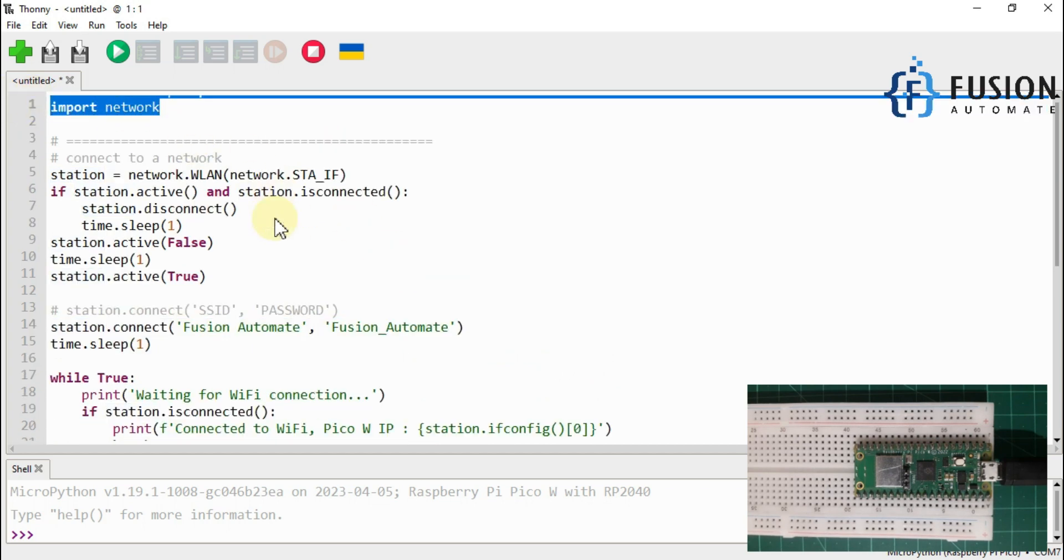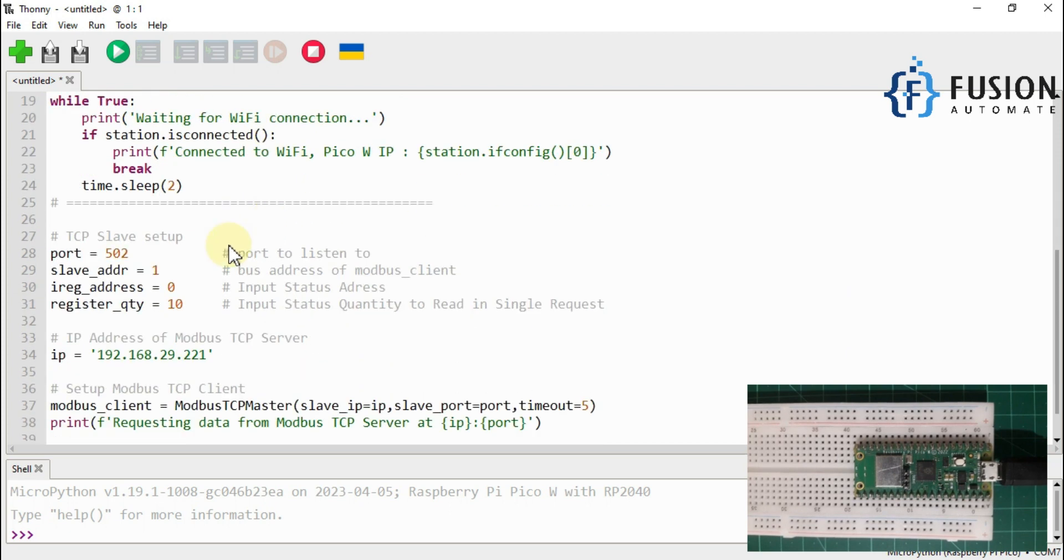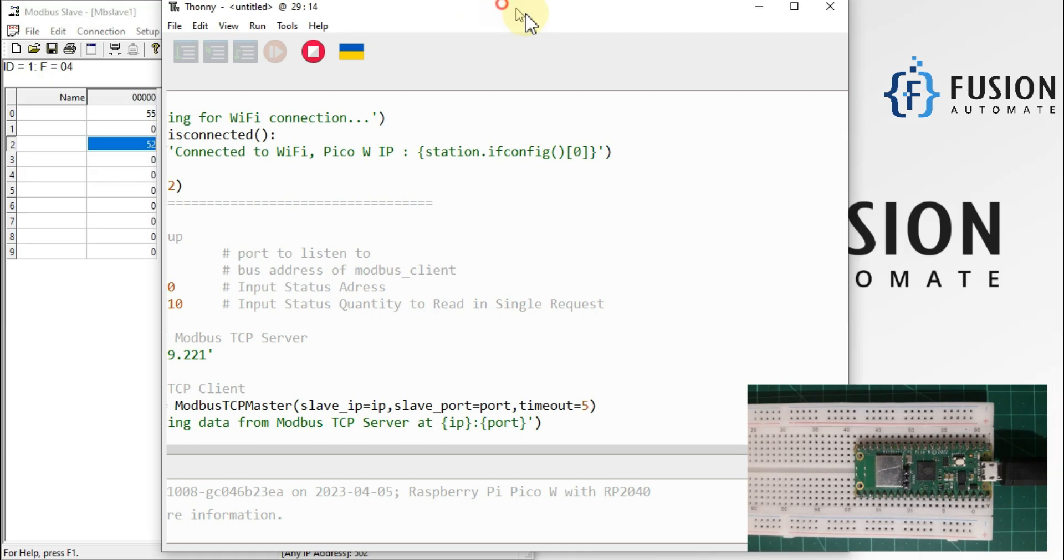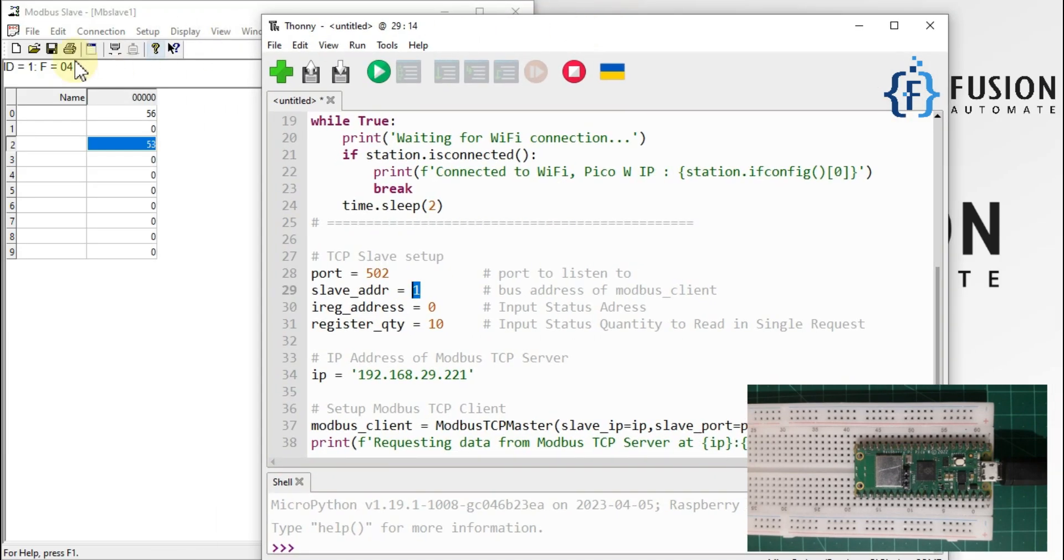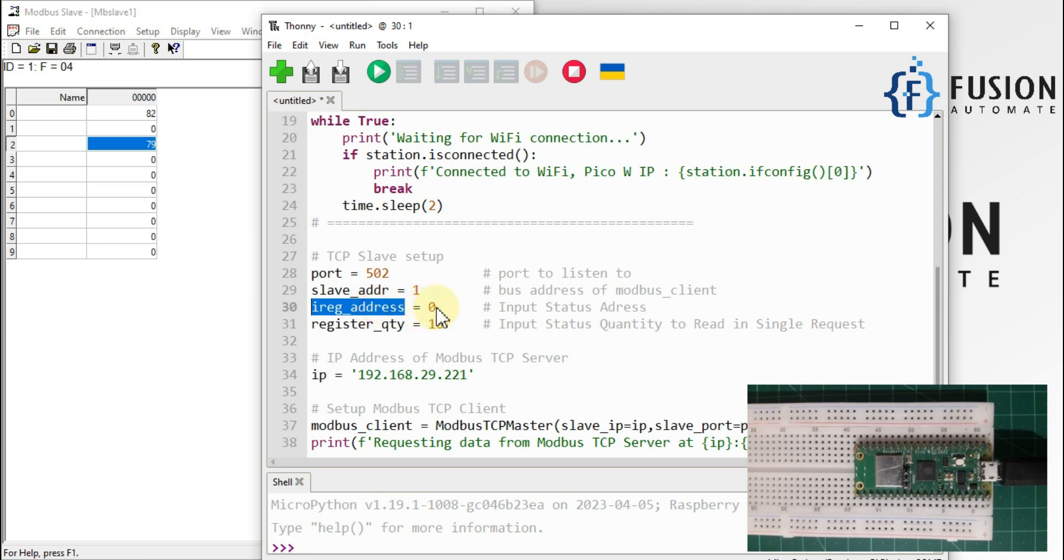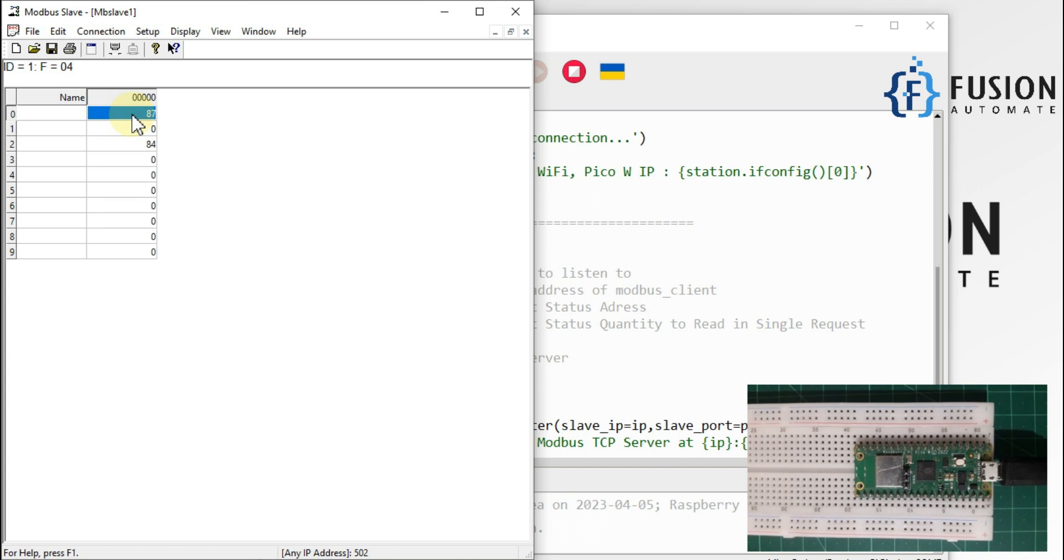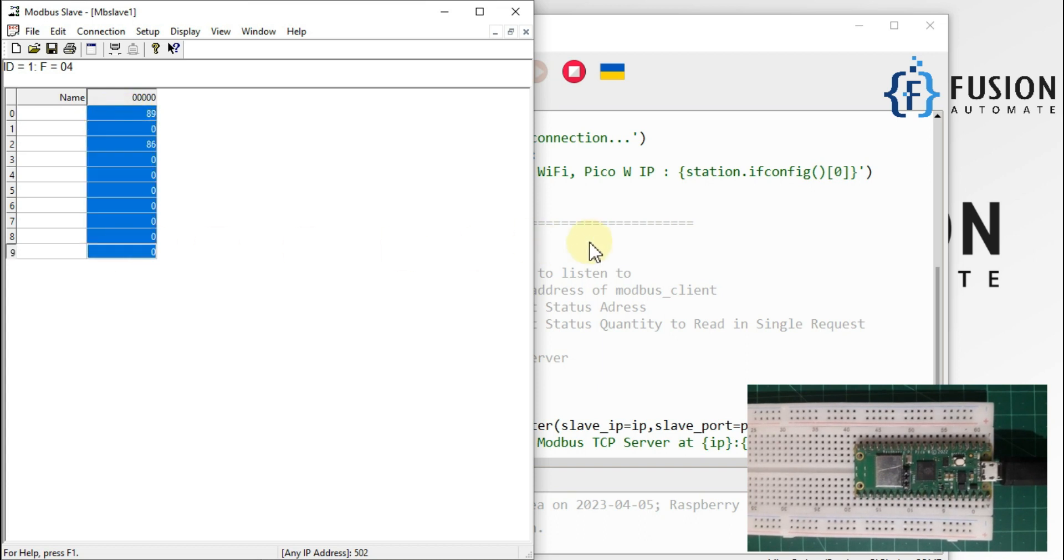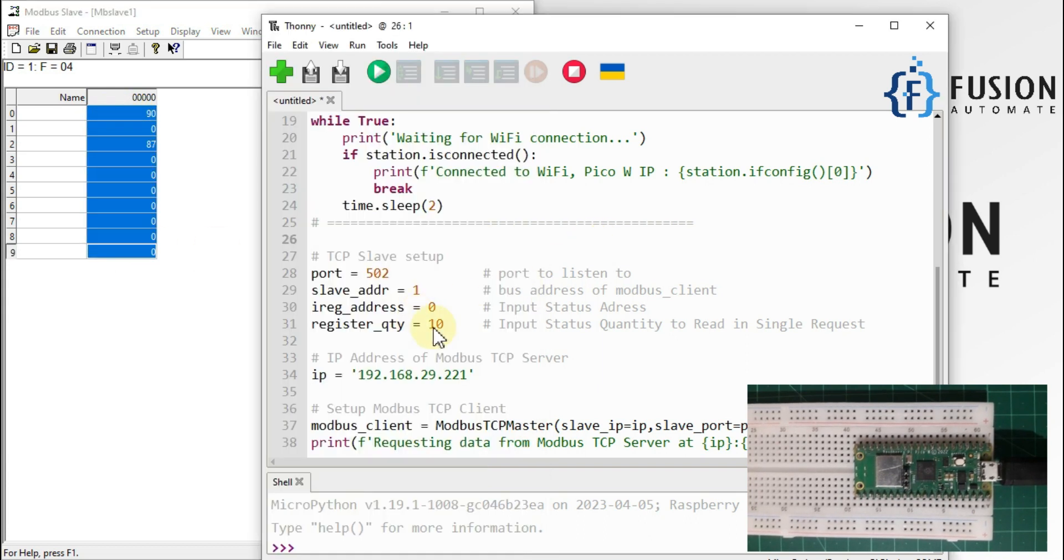And then after, port number 502, standard port for Modbus TCP communication. Slave address is one, so as you can see here slave address is one. Input register address is zero and register quantity is 10. So we will try to read from input register 0 up to 10 quantities. If you want to change the quantity or if you want to change the starting address you can change it from here.